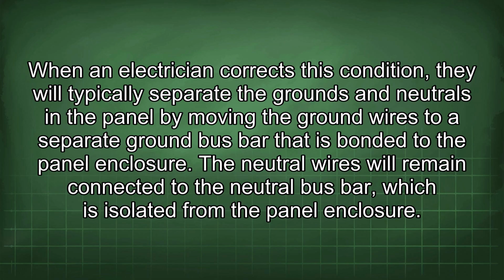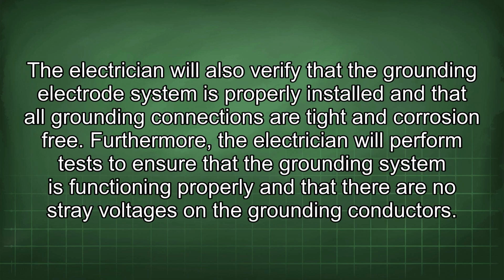When an electrician corrects this condition, they will typically separate the grounds and neutrals in the panel by moving the ground wires to a separate ground bus bar that is bonded to the panel enclosure. The neutral wires will remain connected to the neutral bus bar, which is isolated from the panel enclosure. The electrician will also verify the grounding electrode system is properly installed and that all grounding connections are tight and corrosion-free. Furthermore, the electrician will perform tests to ensure that the grounding system is functioning properly and that there are no stray voltages in the grounding conductors.